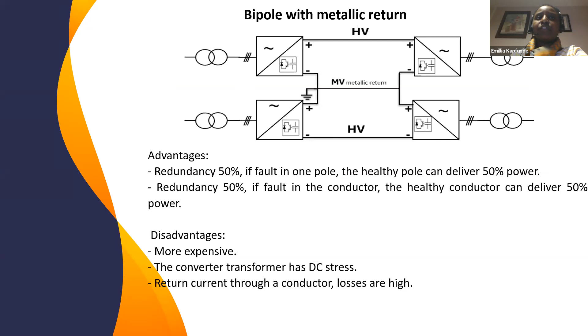So in this topology, they're asking whether the return currents for the two poles of the bipole are in opposite directions such that there is a net current only when there is an imbalance between the two poles. Ideally it will be balanced, but sometimes there is a difference between the sending and return currents, so there is a small current difference, but ideally it should be zero.